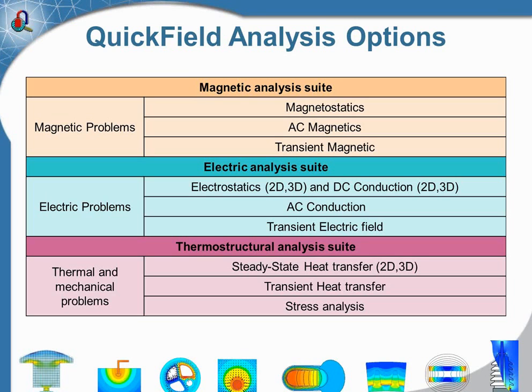At this slide we see types of analysis offered by QuickField. Many of these formulations may be required for high-voltage engineering simulations. Electrostatic analysis may help to estimate electric stresses and risks of electrical breakdown of the insulation at DC or slow-varying voltages. For AC voltages, electric field distribution may be analyzed using the AC conduction model. And if there is a pulse of power, transient electric and transient magnetic models allow defining arbitrary waveforms and analyzing how the voltages and electric stresses vary in time.